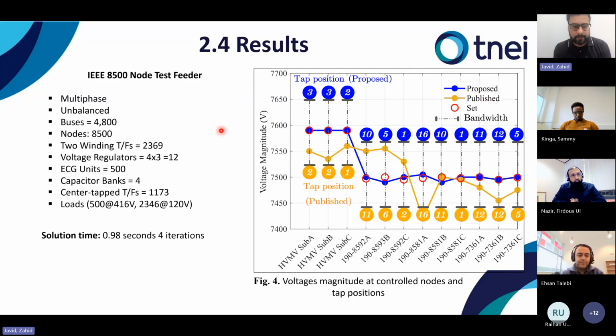So we solved this network in 4 iterations in less than 1 second. And in figure 4, we compare the results of the control nodes of the voltage regulators. The one in blue is the proposed method, the one in yellow is the benchmark, which is the published results, and the red one is the set value. So we can see that, and this is the bandwidth of the voltage regulator. So if anything is between this, it means that it is acceptable. But we can see that with the proposed method, we are very close to the set value, even with more accurate results as compared to the benchmarks.